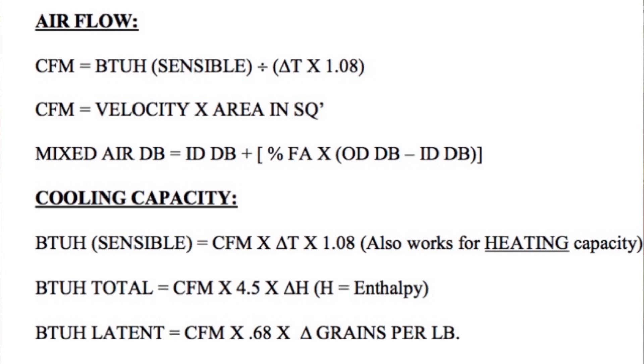Now we're getting into the neighborhood of those really high outputs, and you can understand why a lot of these furnaces are oversized — that is a heck of a lot of heating. I've never seen a house with a zone or whole house that had a capacity that high. That's just one way to use the sensible heat formula.